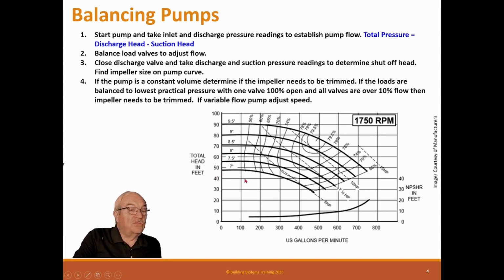Well, you just use percentage. So if you need to change a percentage, if between this and that you got 10 points, you need a certain percentage, then just percentage the difference between the lines, the same percentage, and you'll come up to the tenth you need. It's not too hard to do, and cheat just a little, and I always add a tenth of an inch to it. So just in case there's anything leeway at all, I've still got enough water to do what I need to do. So that's how you balance a single pump.